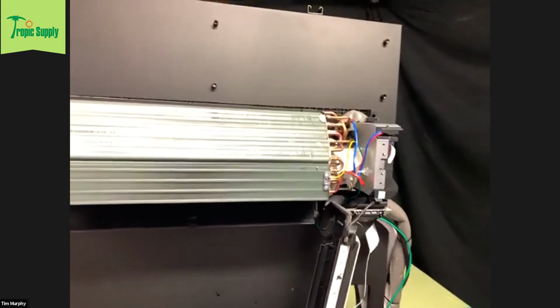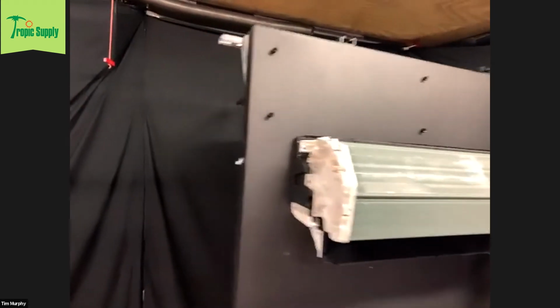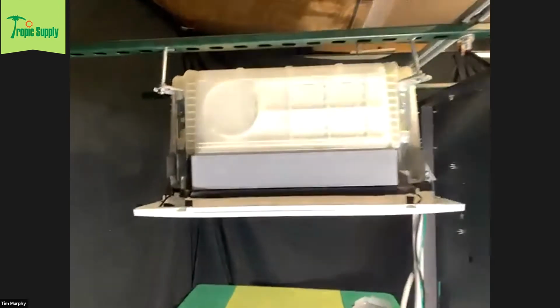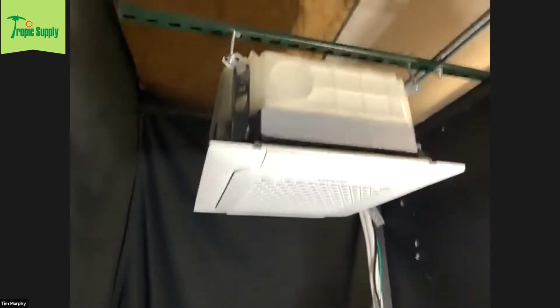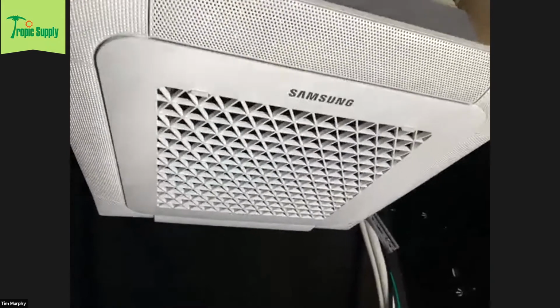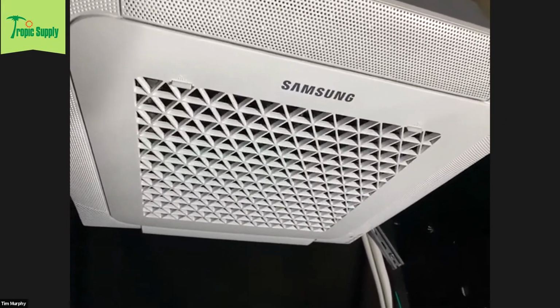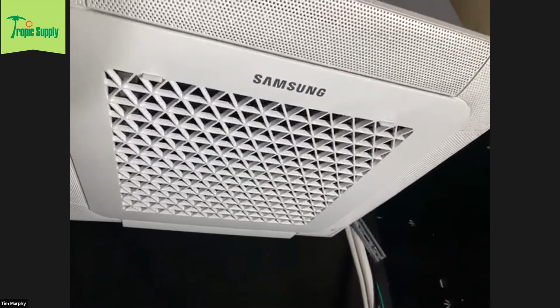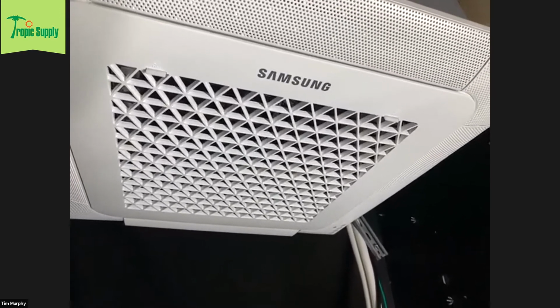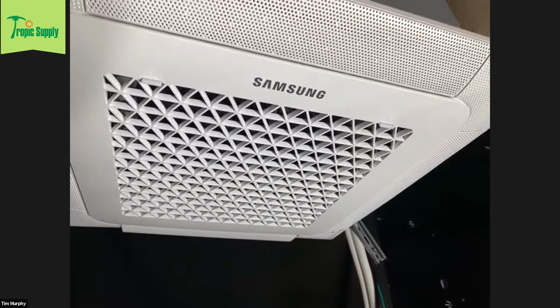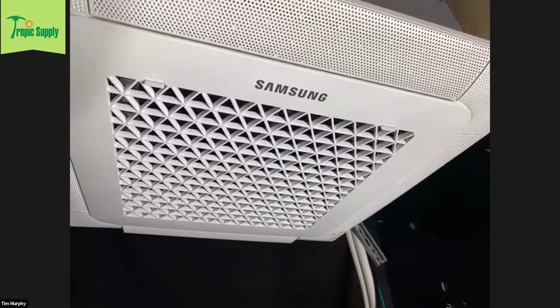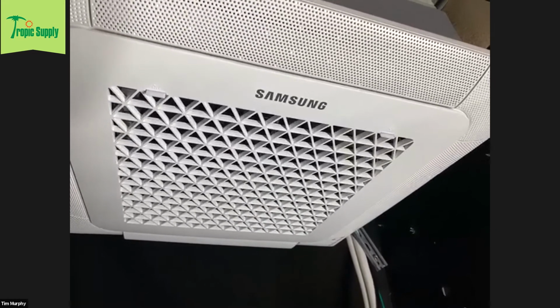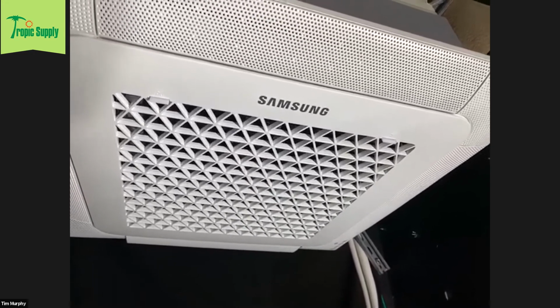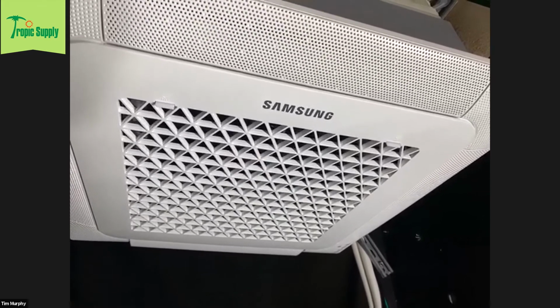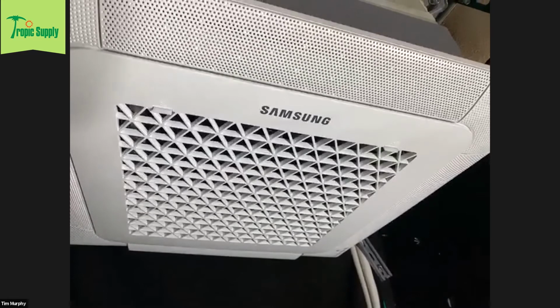Also, while you're getting ready to go over to the cassette, I want to point out that the Quantum 2.0 also has an auto clean feature. When you set that, once the call for cooling ends, the fan will continue to run and monitor the load on the blower, the humidity, and conditions inside the unit. It'll keep running anywhere from 10 to 30 minutes until it's completely dried the coil and blower wheel, then the unit shuts off. You don't have to activate auto cleaning, but once you do, it'll run every time the unit cycles off to dry the unit out and help keep the system clean.